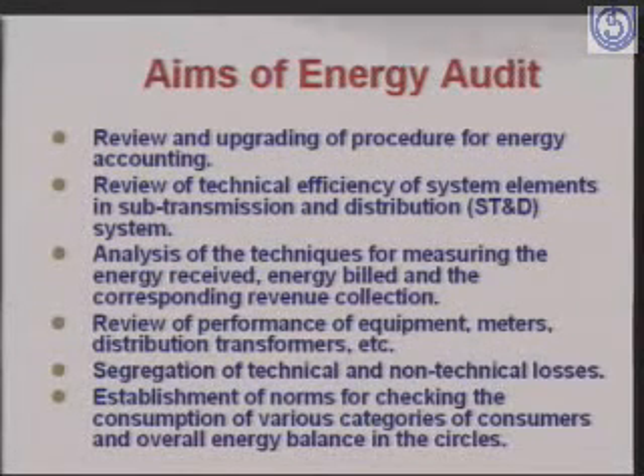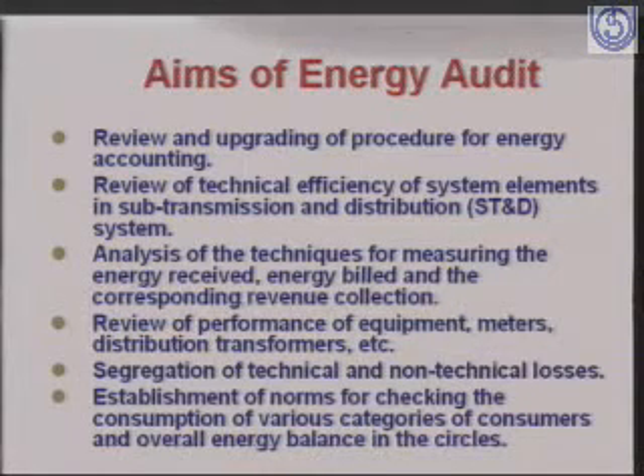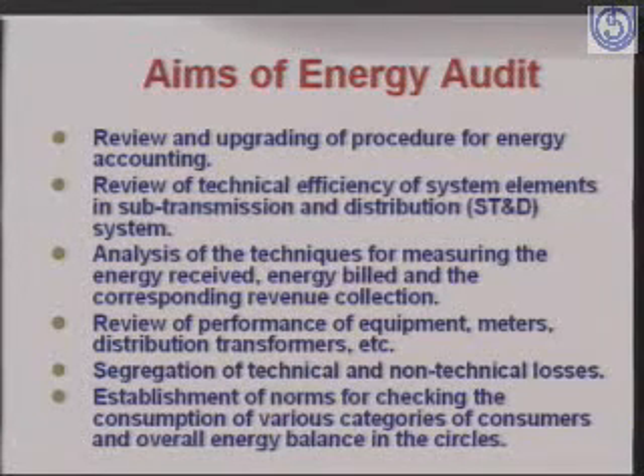What are the aims of energy audit? Basically, these are the main aims. We try to review and upgrade our procedures for energy accounting. The second aim is that we review the technical efficiency of system elements in the sub-transmission and distribution system. For example, we would be working out our transformer losses at the operating loading conditions and the line losses. Third is analysis of the techniques for measuring the energy received, energy billed and corresponding revenue collection. In this we look into the existing practices and try to improve them. Then we review the performance of equipment, meters and distribution transformers. Then we segregate technical and non-technical losses. And finally we establish the norms for checking the consumption of various categories of consumers and overall energy balance in the circles.